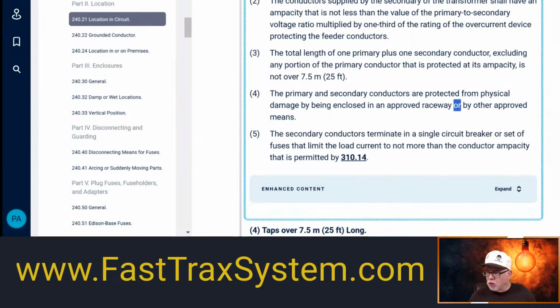And notice it says or, so it can be an approved raceway that they're happy with. Typically, if it's listed and it's going to protect against physical damage, that would be like EMT, rigid, things like that, that do protect against physical damage. Using this rule, they're saying, okay, we approve that raceway. And then, of course, it could be or by other approved means. So an AHJ could look at the situation and say, you know what? I don't care about you needing an approved raceway to do this. We'll let you use something else, okay? That's up to the AHJ's discretion.